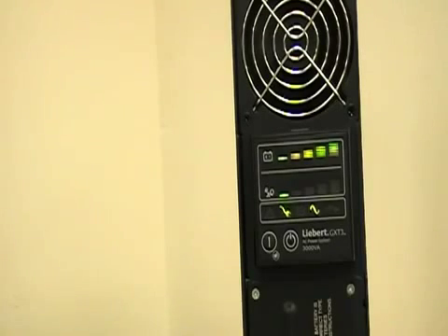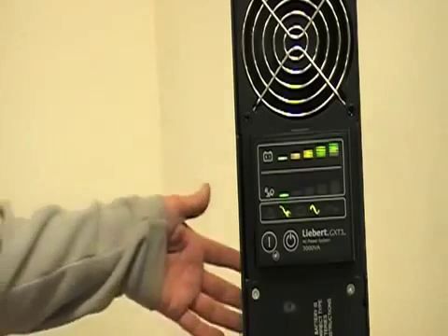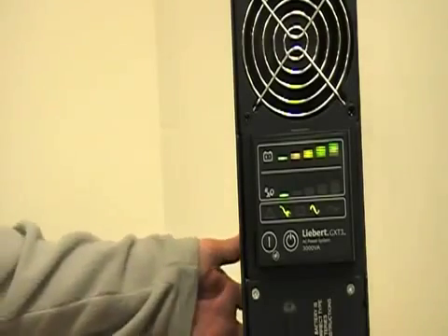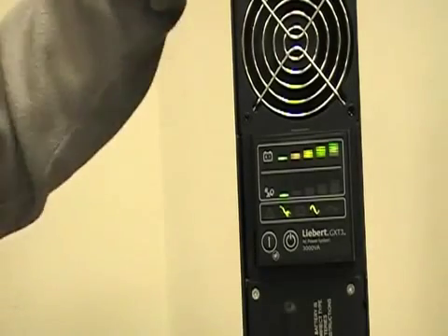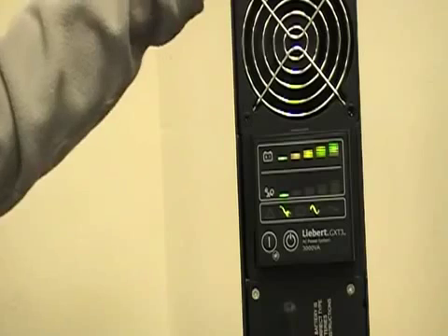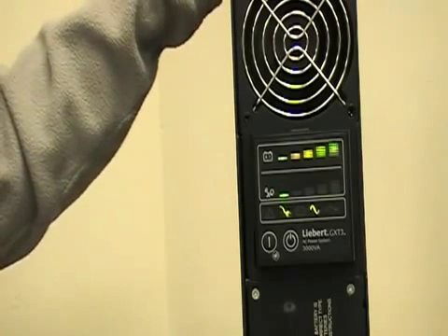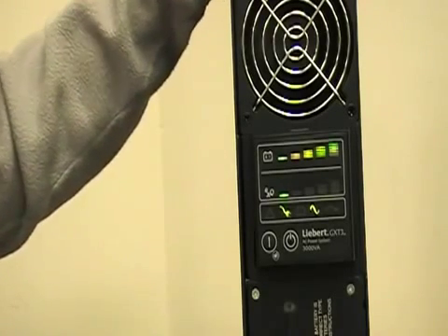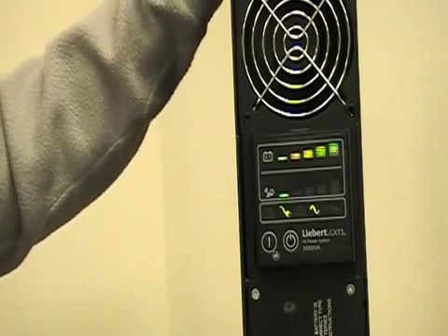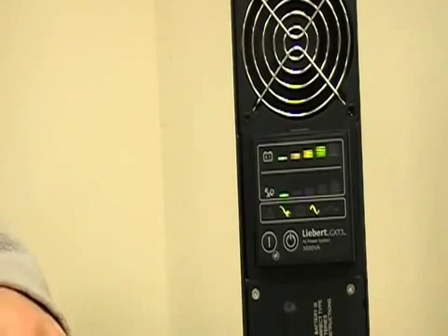At this point, all of your controls, if anything needs to be plugged in, you plug those in now. Of course, we need to do all of our checks on our polarity for the plug cords before you do any cord plugging in. Make sure your cords have the proper plug ends. Then you need to check those for proper polarity out to the switchgear.